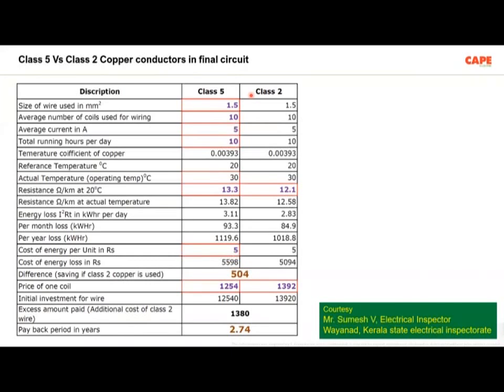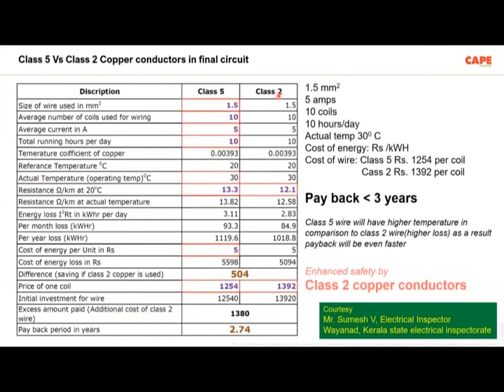Sometimes in the manufacturer's catalog, they have written that the current rating of the wire is 15 amperes. But you cannot use that wire for 15 amperes always. You have to apply the derating factors depending upon the length, depending upon the filling in a conduit, and so on. So in all these cases, class 2 copper is considered, whereas in India, we always use class 5 copper conductor, which has a higher resistance. Somebody asked me what is the energy loss and what is the payback period if we change from class 5 to class 2 conductor? So I just calculated, not me, it is done by Mr.